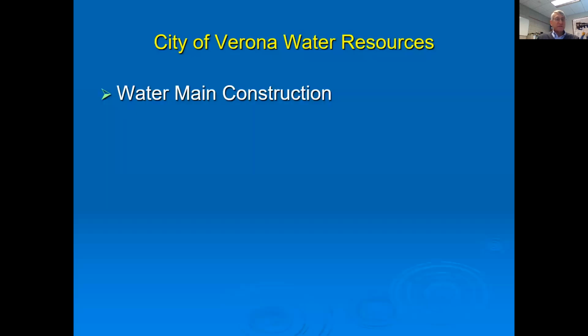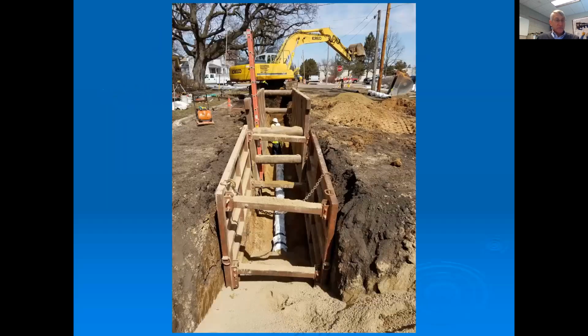Water main construction. Typically, water mains are at least 7 feet into the ground, maybe a little deeper. If you're seeing metal pipe and you're seeing the contractors wrapping that in this white plastic, then you know that's water main construction going on. The pipe is bedded in limestone screenings, and then the trenches are backfilled, and then ultimately the surface is placed on.